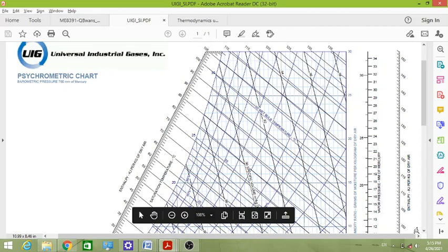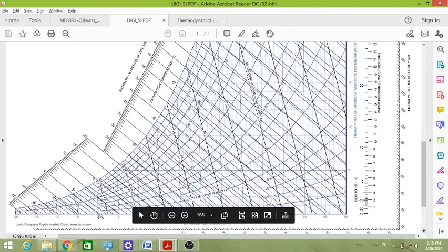And the curve reading, you can see the last curve reading, it is also starting from -15, -10, -5, 0, and this curve reading is called wet bulb temperature. When it goes beyond this, and if it is touching here, it is also called dew point temperature. It goes up to 30, on the equally spaced slant lines.